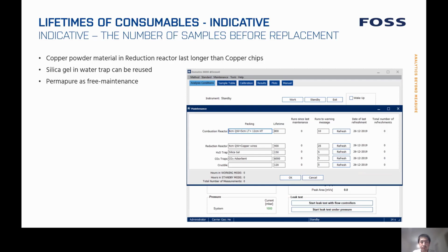It's quite efficient at removing moisture in this system, and because it's maintenance free, you don't need to pay much attention to it. When the 2-year lifetime is up, you just change it. And now I will replay the videos so you will see the detailed information on how the consumables can be changed for this instrument in daily operations.